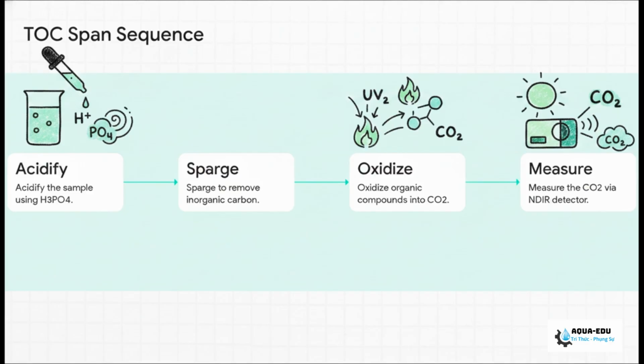It's a 4-step process inside. First, it acidifies the sample with H3PO4. Second, it sparges it with a carrier gas to strip out total inorganic carbon. Third, it oxidizes the organic compounds into CO2 using UV or heat. And finally, it measures that CO2 via the NDIR detector to calculate your TOC.